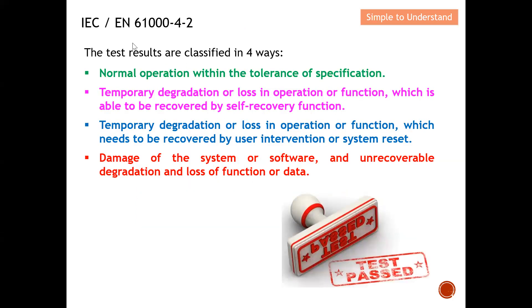The test results can be classified into four categories. Category one: normal operation within tolerance — the EUT operates normally through all positive and negative discharges, meaning all tests are compliant. Category two: temporary degradation or loss of function that is able to recover by a self-recovery function — for example, the EUT resets itself automatically and restores functionality.